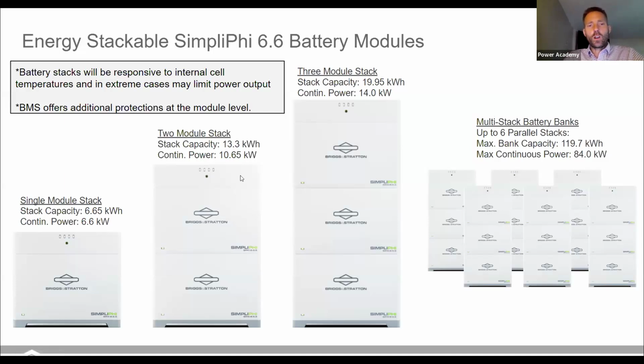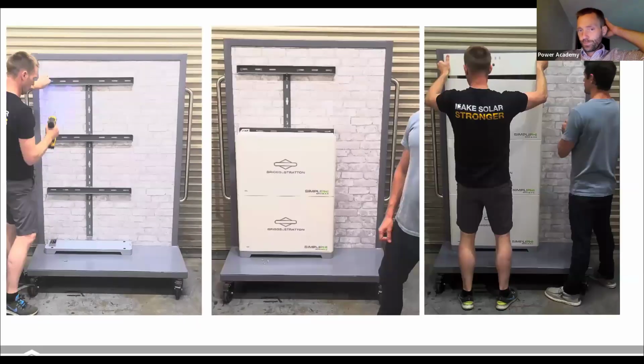So it's a very high power output battery. In stacks of 2, our controller limits us a little bit. We're looking at 10.6 kilowatts of power out of a 2 stack, and out of a 3 stack, we can get 14 kilowatts of power. Note earlier I mentioned that a Sol-Ark 15K is capable of inverting 12 kilowatts from a battery stack. So this battery is more than capable of providing the maximum amount of power that a Sol-Ark can pull from a battery bank. And then if you want more energy storage overall, these are essentially 20 kilowatt hour stacks. If you want more storage, you can parallel up to 6 stacks to get you 120 kilowatt hours of backup. Again, these are wall mountable, parallelable.